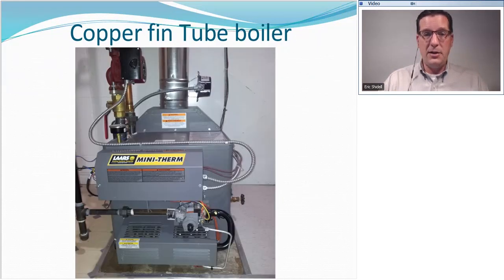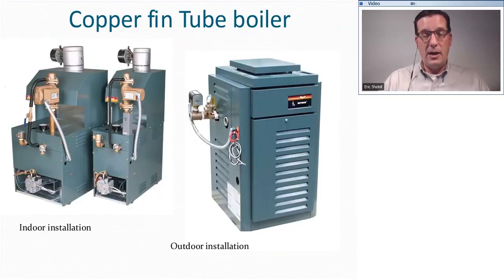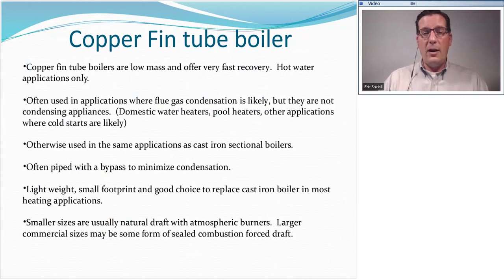Notice this boiler here, it doesn't have a bypass. The manufacturers realized that people aren't putting bypasses on their boilers, so they built one from the factory. That's what this is. It's a bypass. We'll talk more about bypasses later, but I just want you to be aware that copper fin tube boilers, by and large, are supposed to have bypasses between supply and return. They're very lightweight, they have a very small footprint, and they're a really good choice to replace cast iron boilers. They're generally smaller in size, and usually they're natural draft with atmospheric burners. Larger commercial sizes may have some type of sealed combustion or forced draft arrangement, but that's only going to be in the larger sizes.